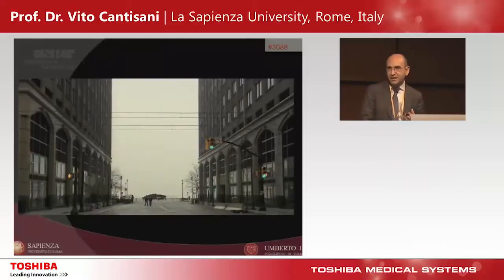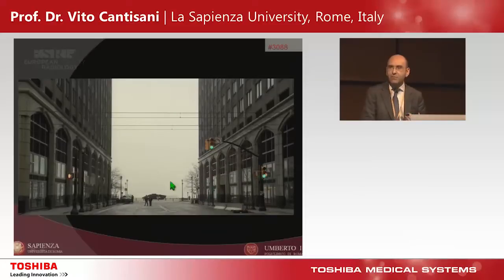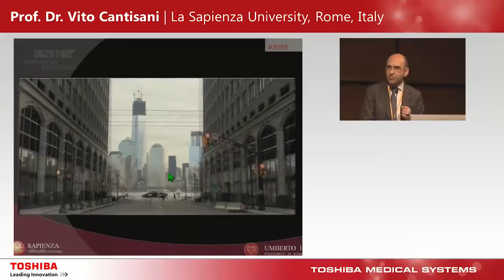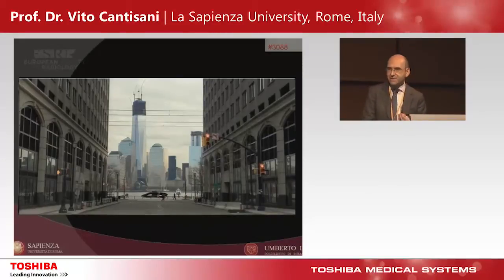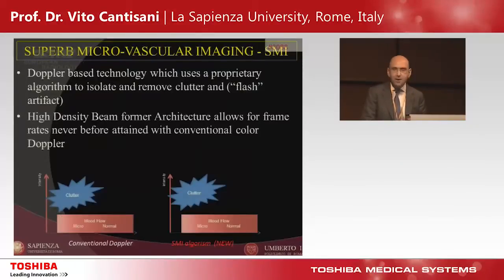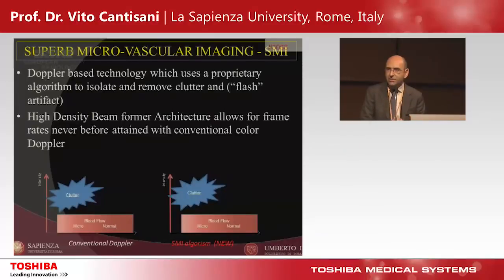It's important to understand what SMI is. Imagine it's 7 a.m. in the morning somewhere in the world — you cannot identify where you are. But when sunshine illuminates the landscape, you recognize Chicago. So what is SMI? SMI is a Doppler-based technology which removes clutter artifacts without reducing the color Doppler information — what I call the 'sunshine color Doppler' evaluation.